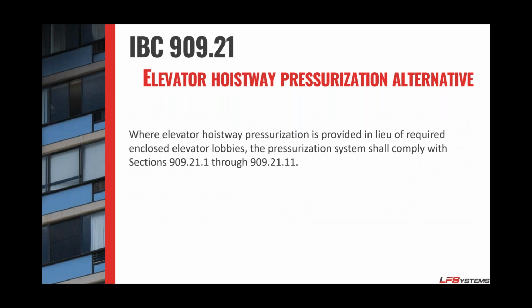So why are we talking about hoistway pressurization anyways? Well, IBC offers this as an alternative to elevator lobbies. In many cases, an elevator will open directly to the corridor, and there's no lobby to prevent the smoke from migrating into the shaft. So hoistway pressurization is available to you as a designer. One thing to point out in 909.21: elevator hoistways have to maintain a min-max of 0.1 to 0.25. That's actually a little bit tighter compared to stairwells. Stairwells are 0.1 to 0.35. So we'll talk about how to handle that.